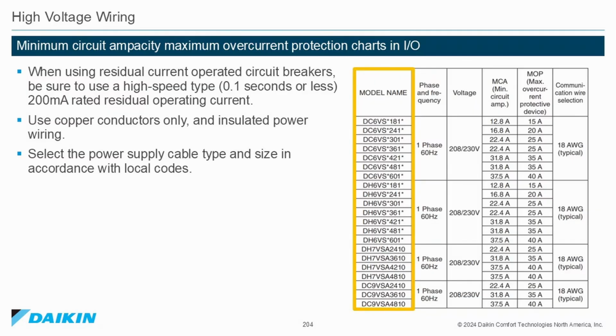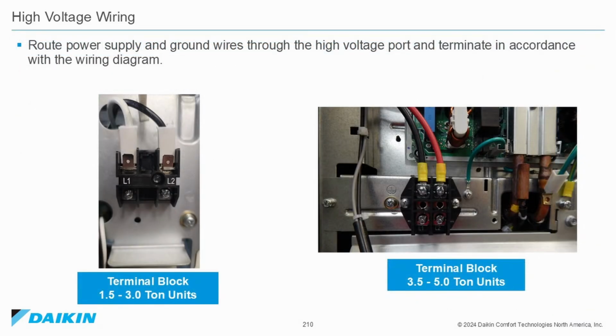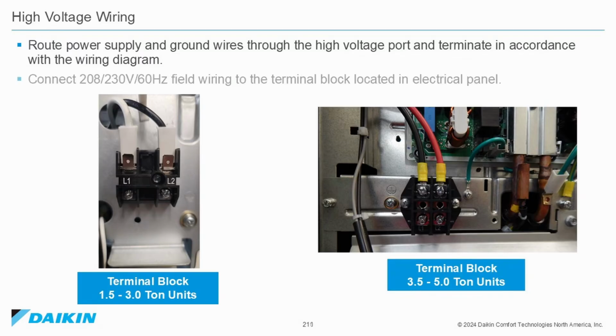This chart shows the model name, the phase and frequency of the system, the voltage, the minimum circuit ampacity, the maximum overcurrent protection, and the communication wire selection. Route the power supply and ground wires through the high voltage port and terminate in accordance with the wiring diagram. Connect 208 230 volt 60 Hz field wiring to the terminal block located in the electrical panel.